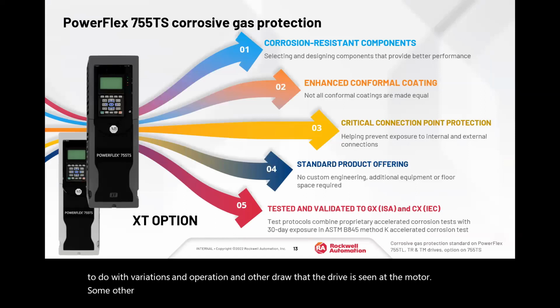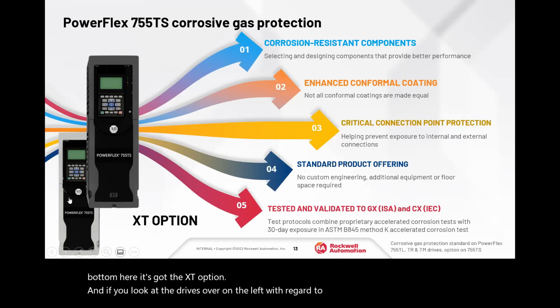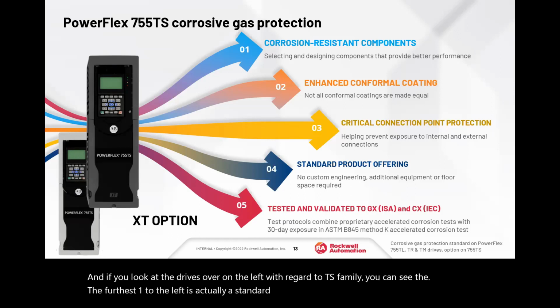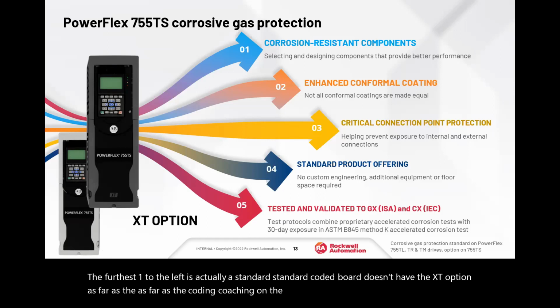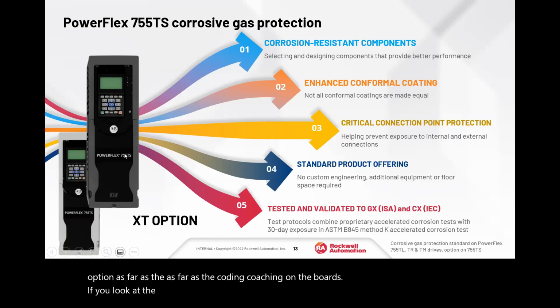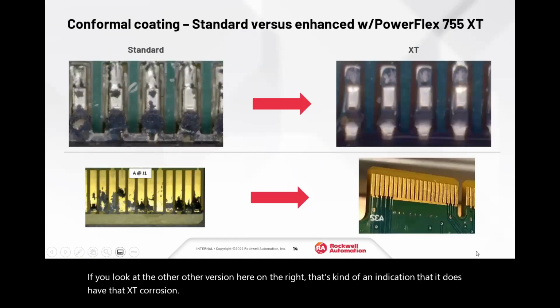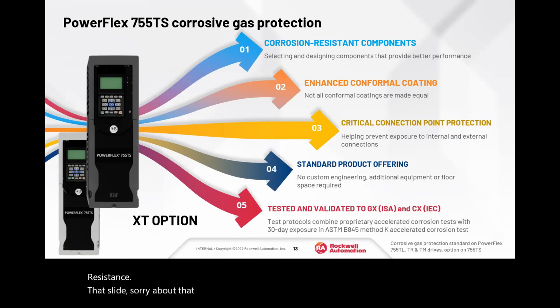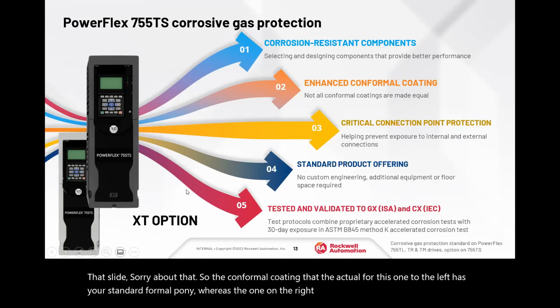Some other things with the 755 and 755 TS and TL. Look down on the bottom here, it's got the XT option. If you look at the drives on the left, with regard to the TS family, the furthest one to the left is a standard coated board. It doesn't have the XT option as far as the coating on the boards. But the other version on the right is an indication that it does have that XT corrosion resistance. I wasn't done with that slide, sorry about that. So the furthest one to the left has your standard conformal coating, whereas the one on the right is where you start getting into the XT.